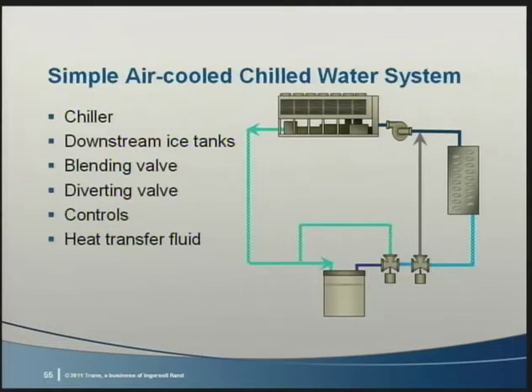This example shows an air-cooled chiller with ice downstream and one pump. The system is quite simple, but it has limitations. Night cooling loads while the tanks are being charged will have to use the cold charge mode chilled fluid temperatures. If the pipes are already insulated, this shouldn't be a problem. What might be a problem is that the window for building ice narrows when there are nighttime cooling loads. Proper examination of the current chiller operation can tell you what your loads are when you want to be making ice.